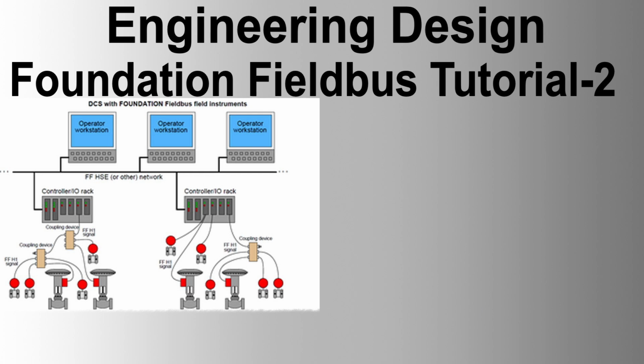Important blocks. AI block, analog input block, is designed to allow users to employ a standard model of generalized signal conditioning functions. An AI block receives data measured by the transducer block and manipulates it for scaling, square root calculation for an orifice plate, low-pass filter, and alarm generation.